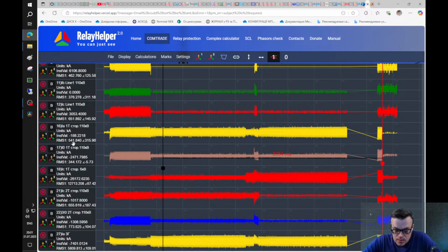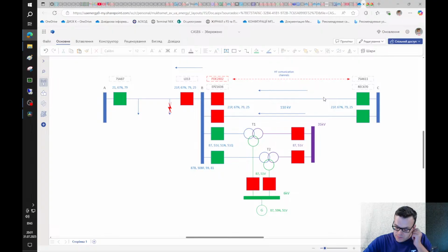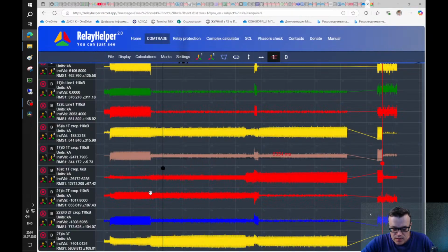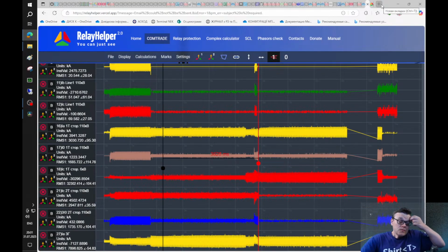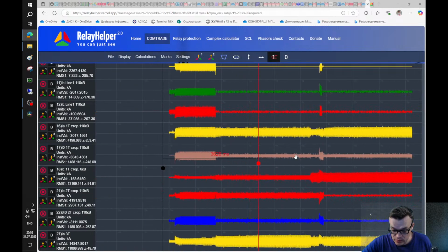The one thing that I didn't mention is that these transformers have a little bit different power. One of them is 40 MVA and another is 63 MVA. That's why the currents differ a little bit. Until that period of time, we believed we can't calculate a negative sequence current because there are not enough channels to calculate it. But we believe that this protection also started because of the timing.